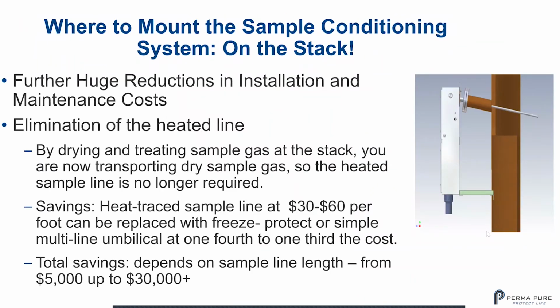So here's a further benefit: where to mount the sample conditioning system on the stack. This gives you a further huge reduction in installation and maintenance costs by the elimination of the heated line. By drying and treating the sample gas at the stack, you are now transporting dry sample gas, so the heated sample line is no longer required. The savings: heat trace sample line at $30 to $60 per foot can be replaced with freeze protect or simple multi-line umbilical at 1/4 or 1/3 the cost. Total savings depends on the sample line length, but from $5,000 up to $30,000+. In fact, the savings can be even more than what the system costs itself. That's what a profound impact this makes.